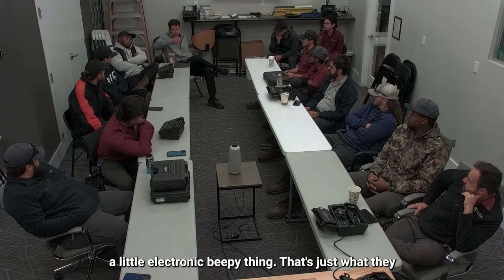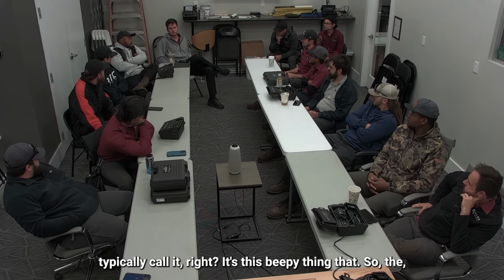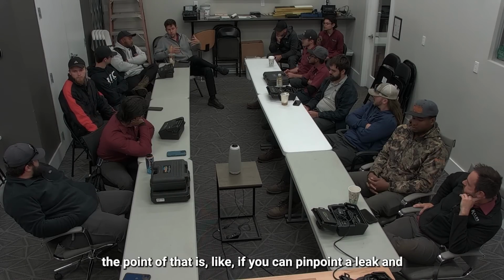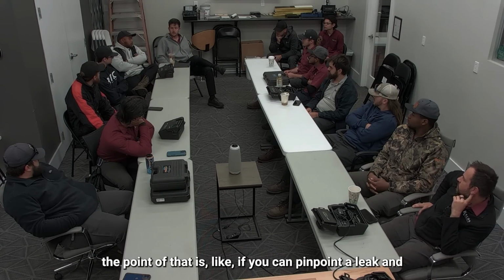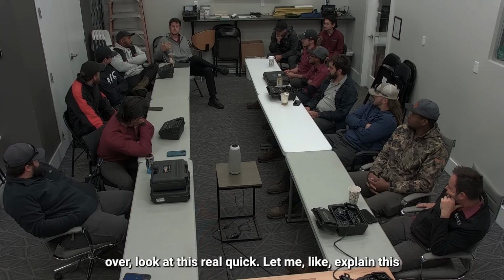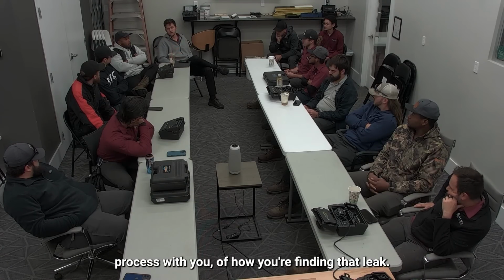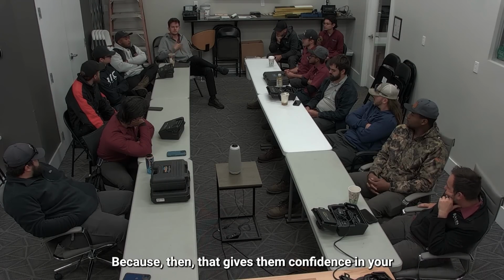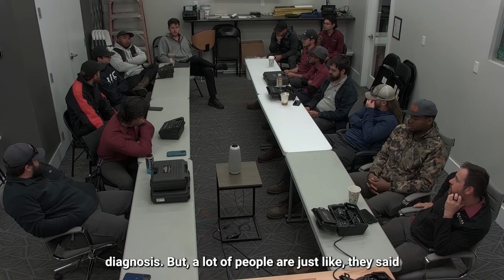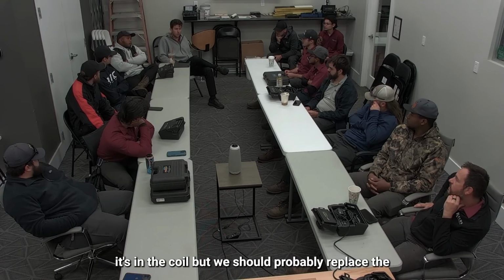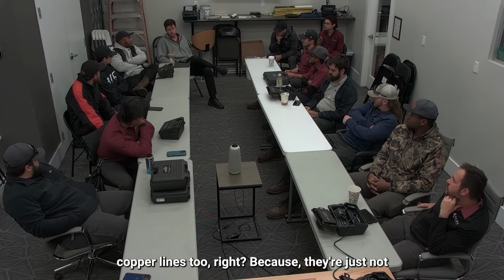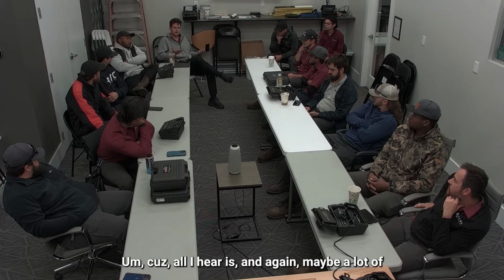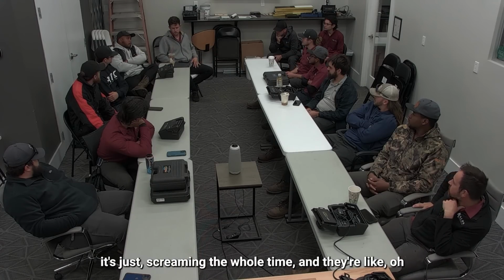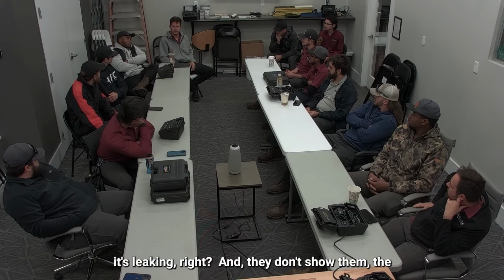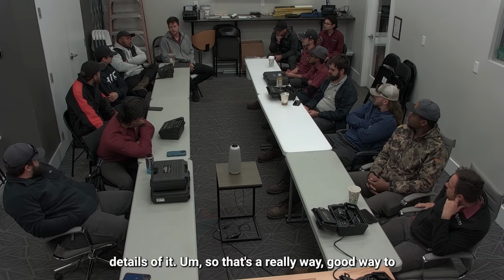When somebody pulls out that little electronic beepy thing, the point is, if you can pinpoint a leak and find it in the coil, I'd always say, come over, look at this real quick. Let me explain this process with you of how you're finding that leak, because that gives them confidence in your diagnosis. A lot of people just hear, they said it's in the coil, but we should probably replace the copper lines too, because they're not confident in the diagnosis. Maybe a technician just pulls one out and it's screaming the whole time, and they say it's leaking, without showing the details.